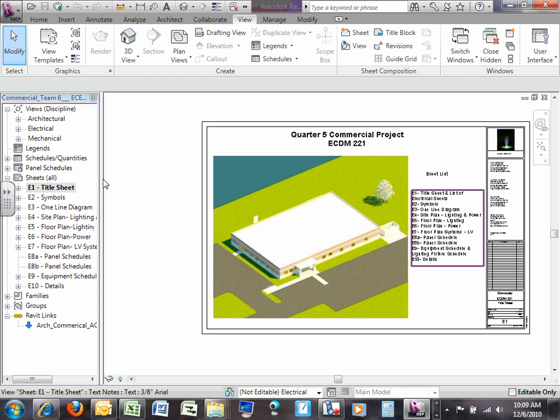We get this understanding, guys, item A all the way through, and item C has multiple items under it, so I'll start with C. C lists all the mechanical equipment that needs to be powered and/or controlled by the electrical contractor. That means I need to specify feeders, disconnects if any, and control systems for all this mechanical equipment, meaning heating, cooling, and ventilation equipment. That's all the mechanical equipment there is.